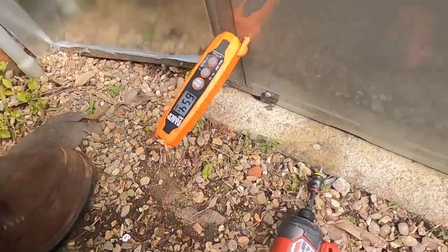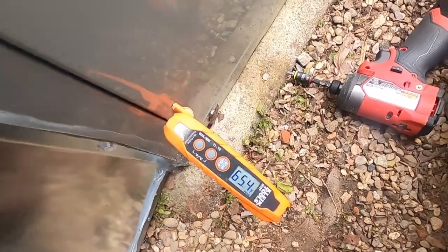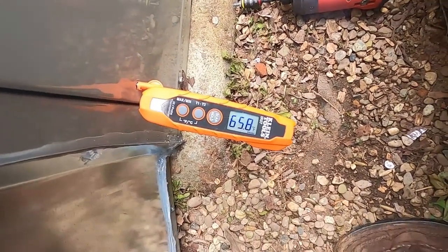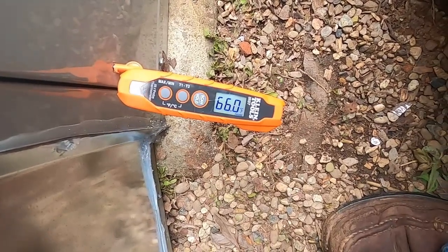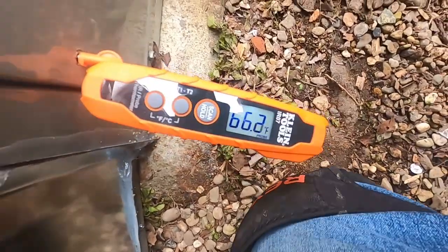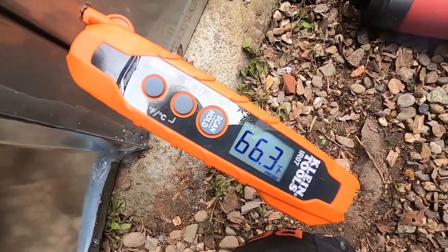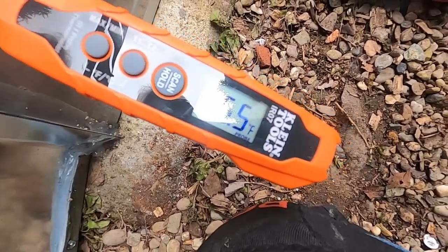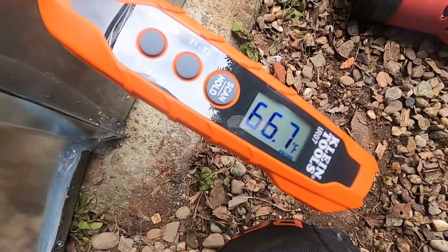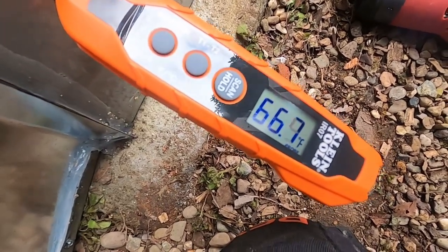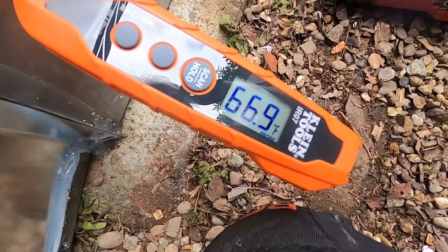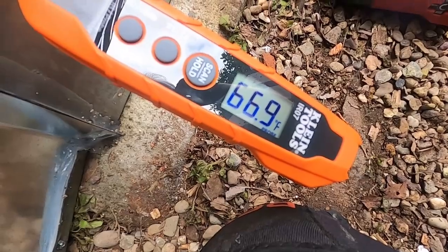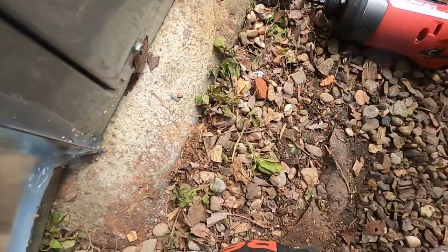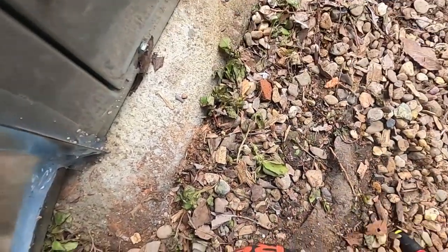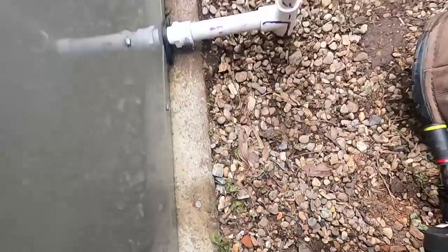So anyway, we're gonna go in here and we will get our return temperature, which is about 66. I mean, it's 61 degrees outside. When I went in there, they had the thermostat set on 67. So evidently they like it chilly in the house, which, I mean, I keep my heat set at 66 anyway. I don't run the heat very hard in the wintertime. But so I've got a 66 degree return. Let's go see what our supply is.